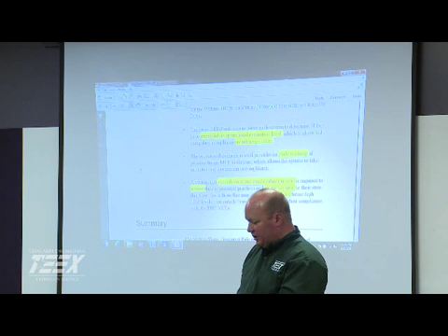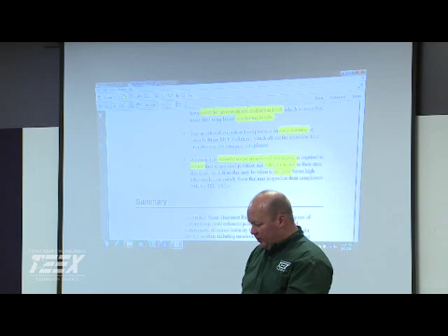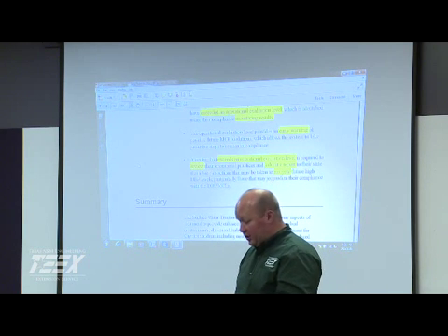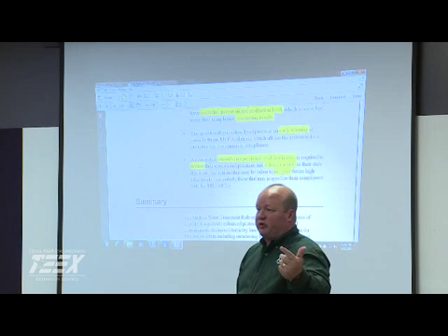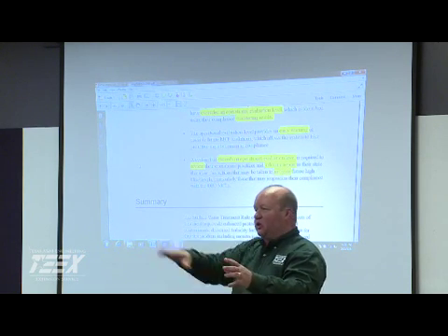And if we start having an exceedance, we're going to have to increase our monitoring, and that's one of the ways that they consider an early warning. Then you're going to have to go in and do a review of your operational system, what's going on with it. You got to submit a report, then figure out how you're going to mitigate it. That's just what we were talking about. You got to increase your flushing, you got to change your disinfection profiles in your system. In your treatment plant, you're going to come out with a lower residual and then boost it somewhere else. What are you going to do to change it?